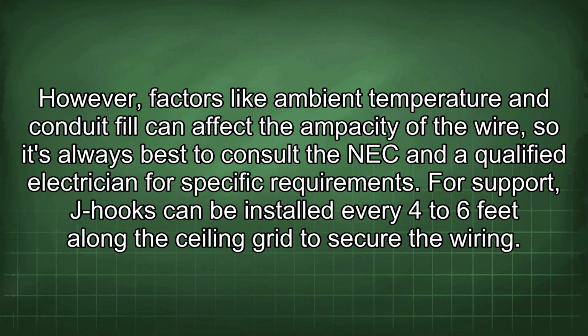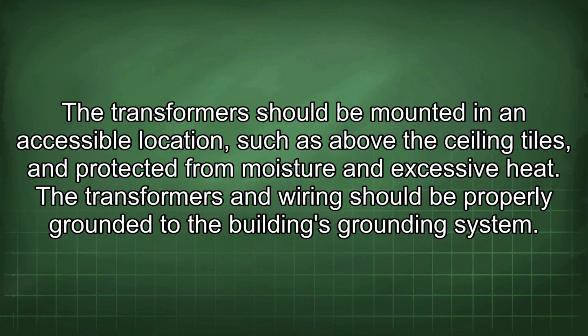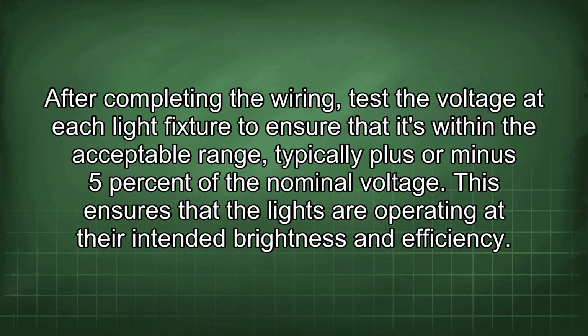The support J-hooks can be installed every 4 to 6 feet along the ceiling grid to secure the wiring. The transformers should be mounted in an accessible location, such as above the ceiling tiles, and protected from moisture and excessive heat. The transformers and wiring should be properly grounded to the building's grounding system. After completing the wiring, test the voltage at each light fixture to ensure that it's within the acceptable range, typically plus or minus 5% of the nominal voltage. This ensures that the lights are operating at their intended brightness and efficiency.